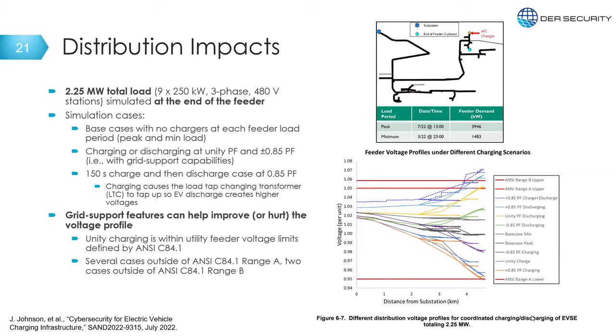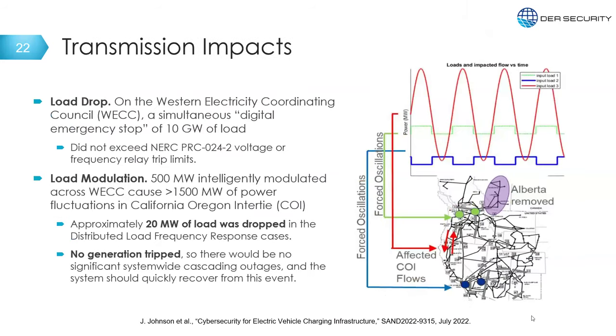And if you use reactive power, you can move the voltage a lot, I won't get into the details. Grid operators are required to maintain that voltage within ANSI Range A limits, which are plus and minus 5%. Why does this matter? It can hurt pumps and do other things. So at the distribution level, grid support functions are great if used appropriately, and can be dangerous if used inappropriately, because they can move that voltage significantly.